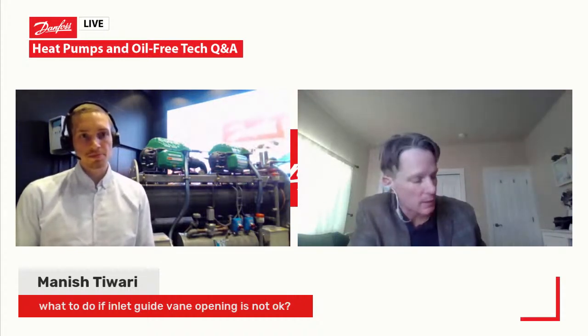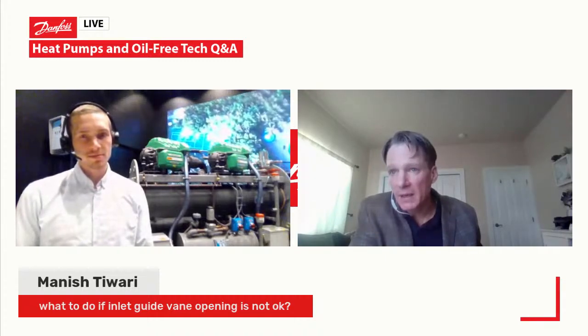Yeah, our service guys will have to help you on that. So if that's a real issue - I'm sorry, who asked that question? That's Manish Tiwari. Okay, Manish, if you can send us an email and let us know specifically what the issue is. If it's locking up, there was a previous issue with some of our inlet guide vane actuators - most of those issues have been addressed either in the field or by the OEMs who build the chillers and heat pump systems with these. But if there's one still remaining out there that needs to be addressed, it's probably that actuator that needs to be replaced, and we have a service bulletin that governs that. So the OEM who built that unit and our service bulletin associated with that should be able to address the issue.